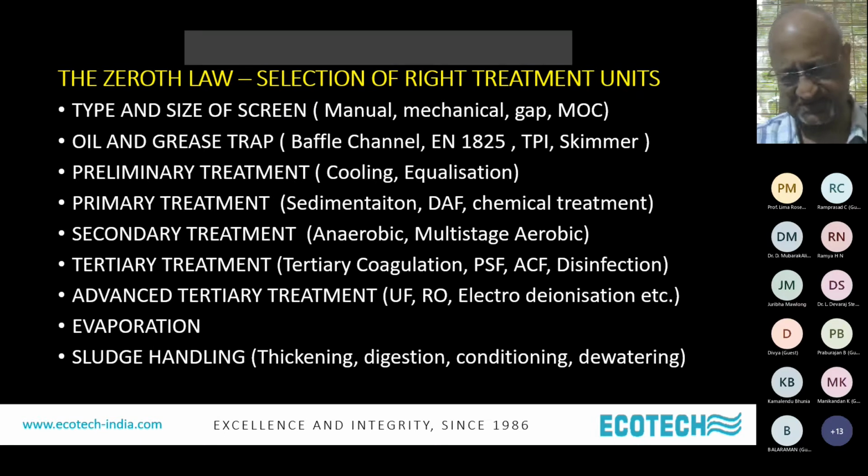And we have used this extensively in Bangladesh because, as I said, our client is in the foods business. And in the foods business, they do a lot of fried snacks and things like that. A lot of oil comes out in the wastewater. TPI or even maybe a dissolved air flotation would be a method of removing these oil and grease, free oil and grease.